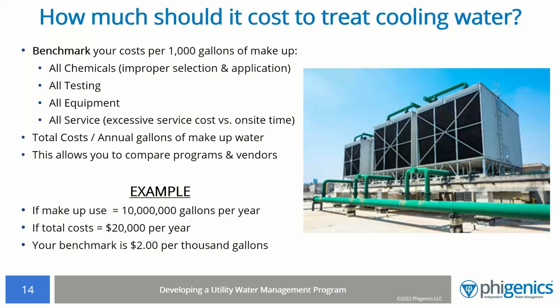You want to add up the costs for all chemicals, all testing, all equipment related to feeding the chemicals, and then all service, divided by your gallons of makeup water times 1,000. So for 10 million gallons of makeup water and a total cost of $20,000, your benchmark cost is $2 per 1,000 gallons. So the question is, have you benchmarked your system, and how does it compare to your regional neighbors?